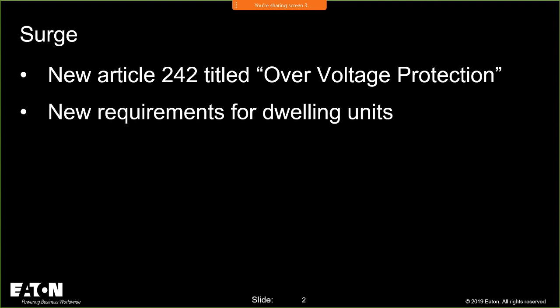242 surge again has a focused article now. It does not add new requirements but consolidates all of those requirements, and it brings future attention around performance requirements. One of the things that's missing, and I don't know where the right home is for it in 242 or 230, is we have surge requirements but we don't really talk about some of the key parameters you need to have with regard to performance.